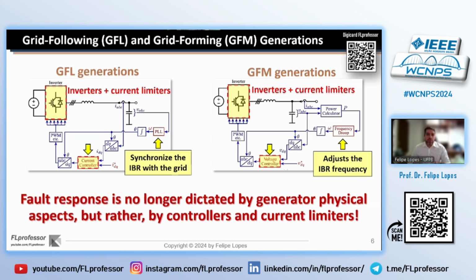And this is very challenging for conventional protections. Similarly, there are a lot of people saying that grid forming generations are tending to solve some of these problems, and this is true. I agree, but we cannot overcome the problem of reduced currents. At least we cannot solve this problem if you are not paying more to have inverters that support higher current levels. But here, these generations will form the grid, and the controllers are a little bit different because they are not current controllers, but rather voltage controllers.